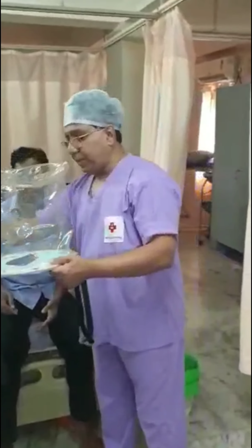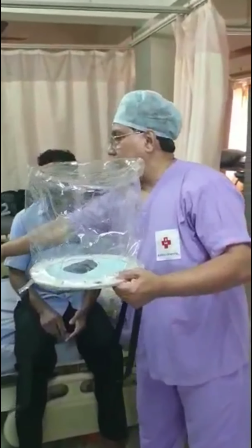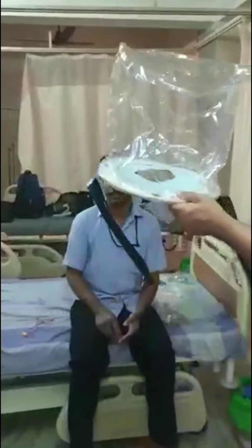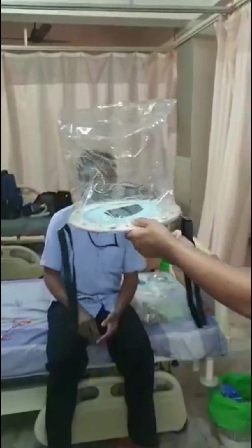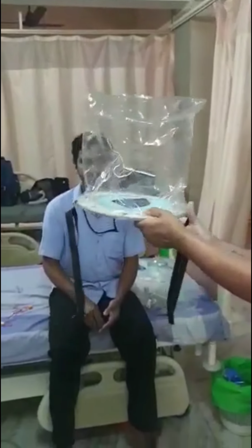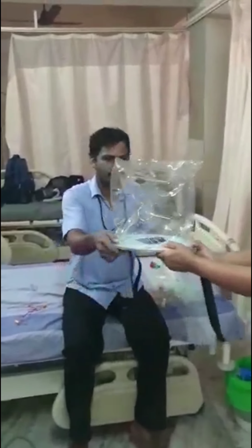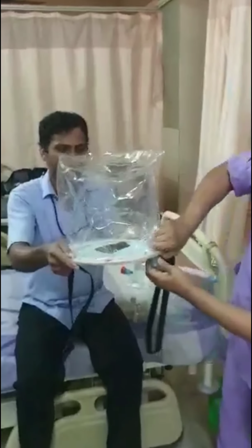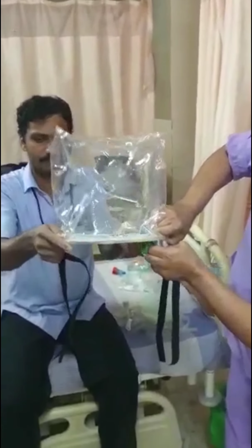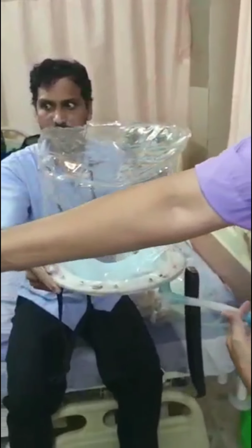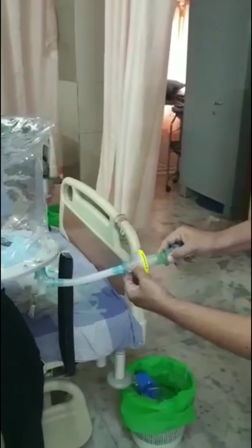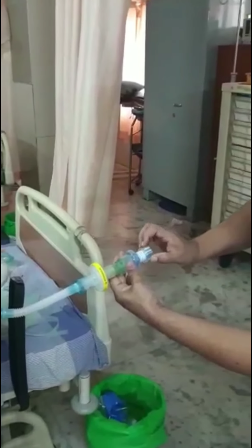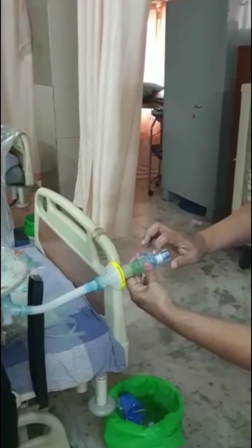Once the hood is opened, we fix one catheter onto one of the ports, and then we fix a viral filter to the other end, and then we use a mechanical PEEP valve and fix it.